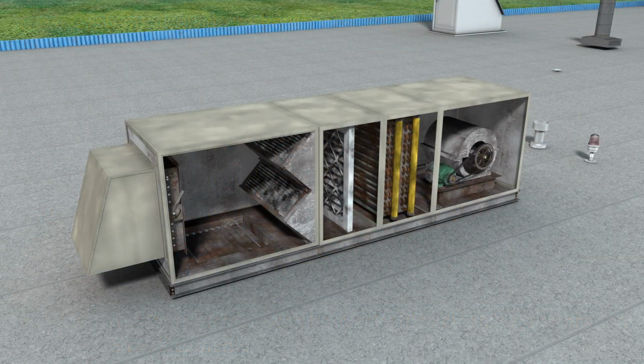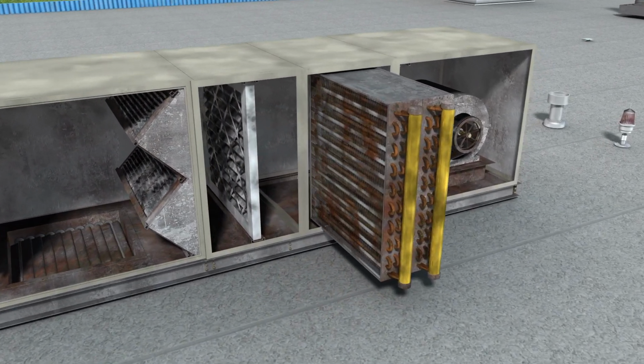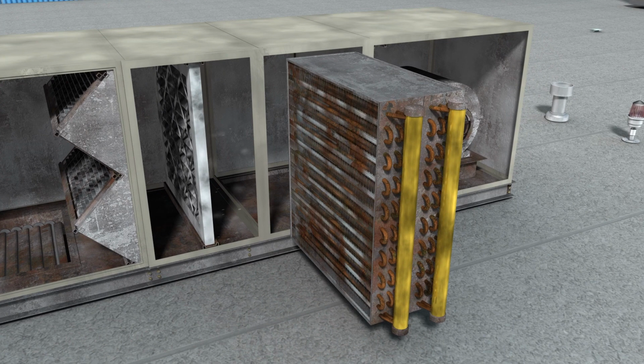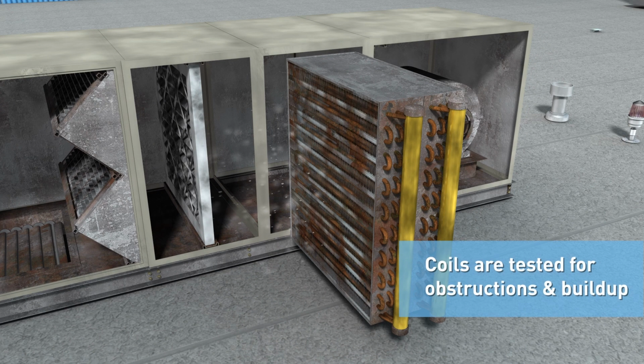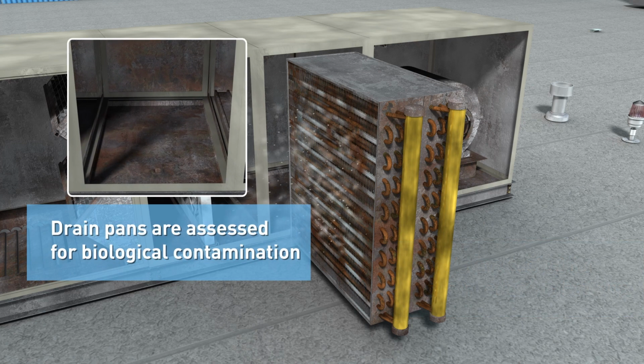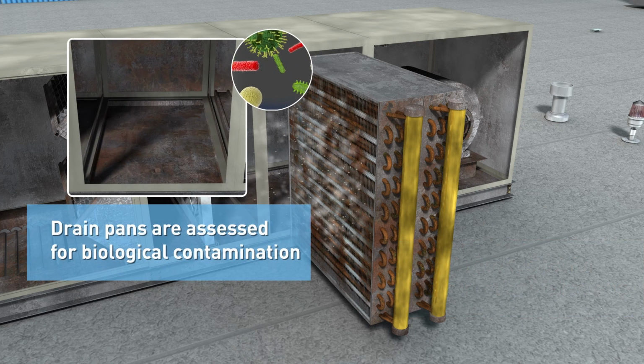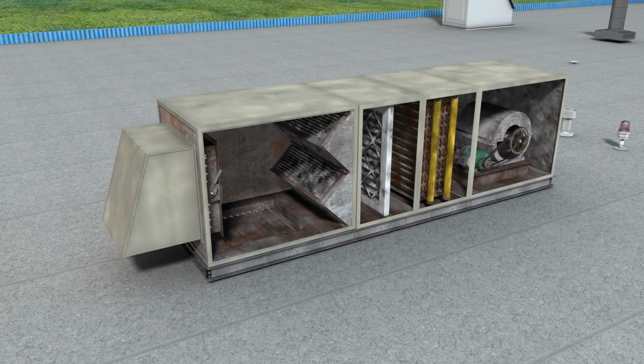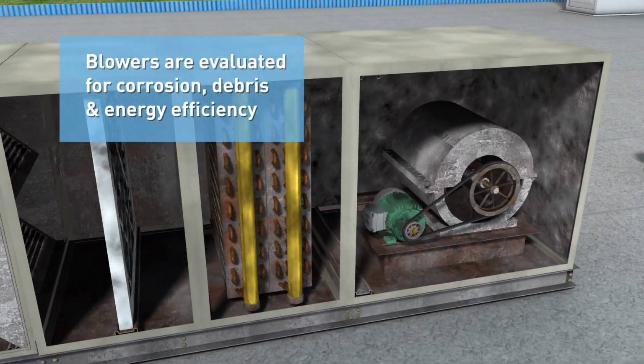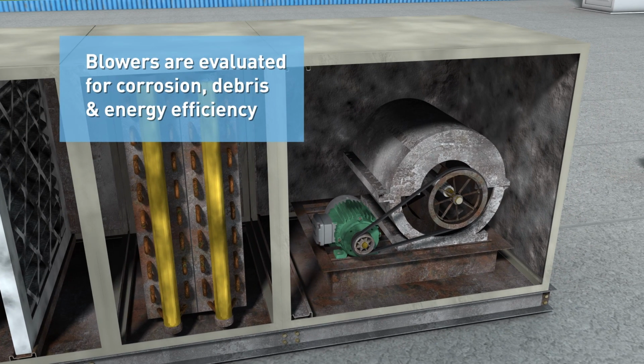The physical, operational, and environmental conditions of the system components are evaluated through specialized testing protocols. Coils are tested for airflow obstructions and particulate buildup. Drain pans are assessed for biological contamination like bacteria, corrosion, clogs, and leaks. Blowers are evaluated for corrosion, debris, and energy efficiency, while fiberglass insulation is checked for material breakdown and sampled for microbial concerns, such as mold.